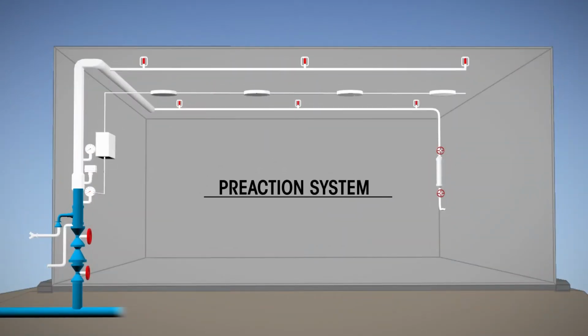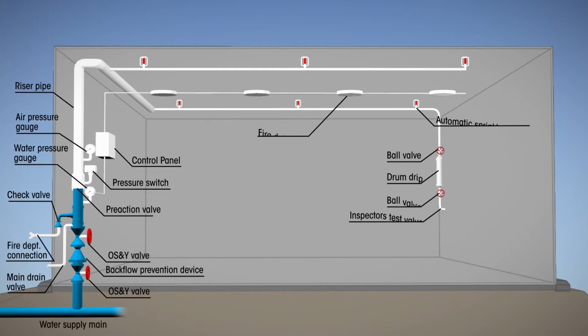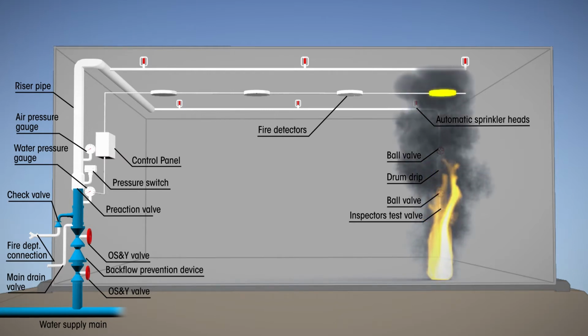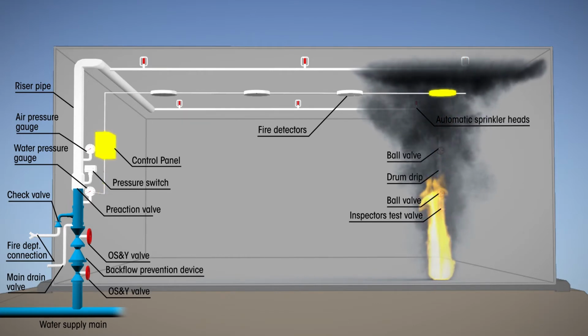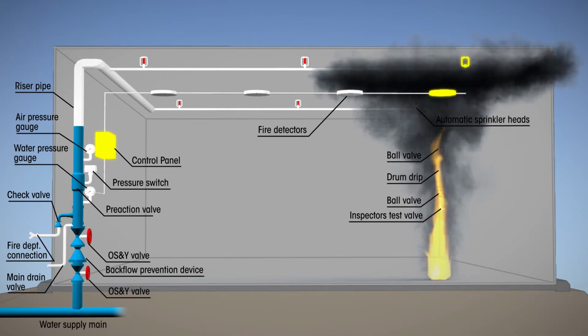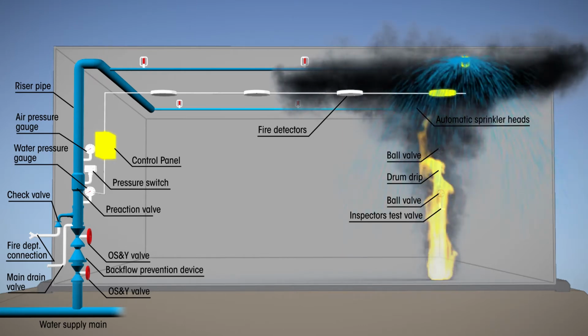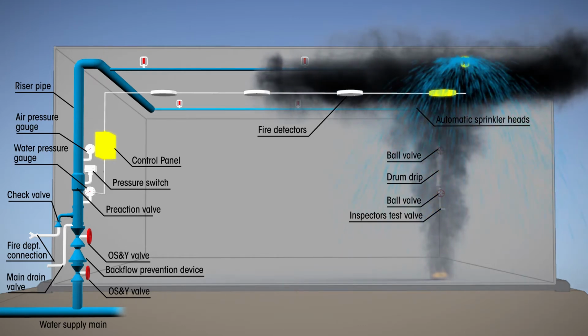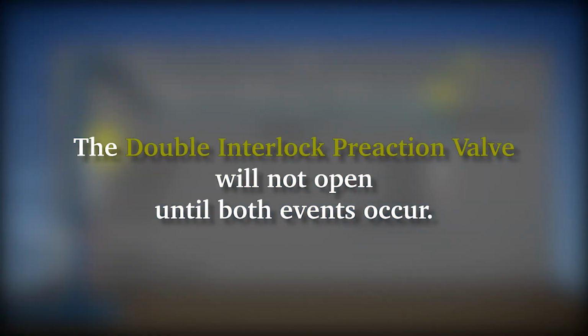Pre-action sprinkler systems have automatic sprinklers that are part of a piping system containing air that might or might not be under pressure, with a supplemental flame, heat, or smoke detection system installed in the same areas as the sprinklers. 2 separate events must occur for fire sprinkler activation. First, the detection system must identify a fire and open the pre-action valve, which allows water to flow into the pipes. Then, a fire sprinkler must activate to flow water on the fire. In the case of a double interlock pre-action system, to avoid unintentional detector operation, the pre-action valve will not open and flow water into the pipes until both events occur.